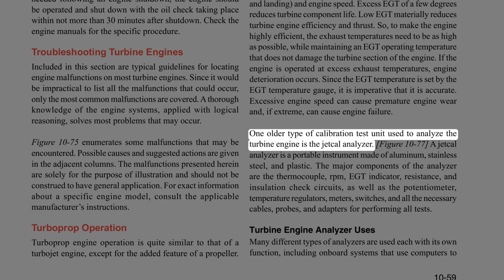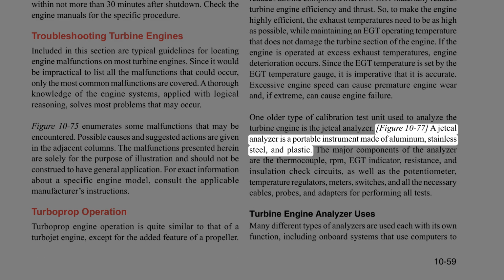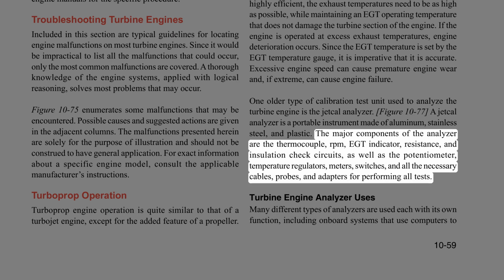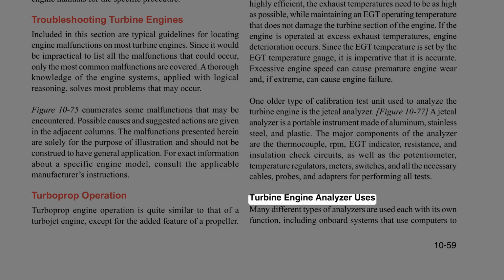One older type of calibration test unit used to analyze the turbine engine is the JetCal analyzer, Figure 10-77. A JetCal analyzer is a portable instrument made of aluminum, stainless steel, and plastic. The major components of the analyzer are the thermocouple, RPM, EGT indicator, resistance, and insulation check circuits, as well as the potentiometer, temperature regulators, meters, switches, and all the necessary cables, probes, and adapters for performing all tests. Turbine engine analyzer uses.